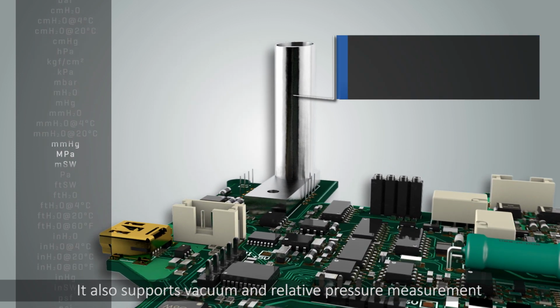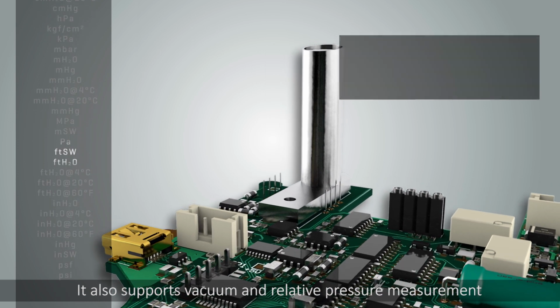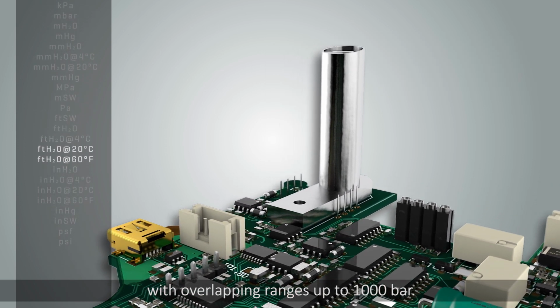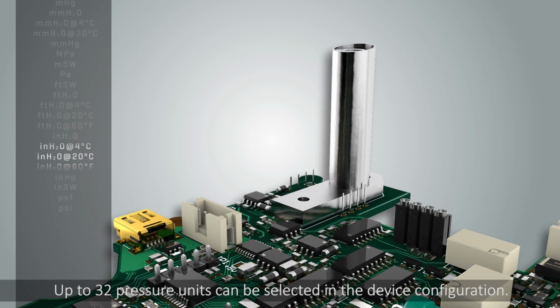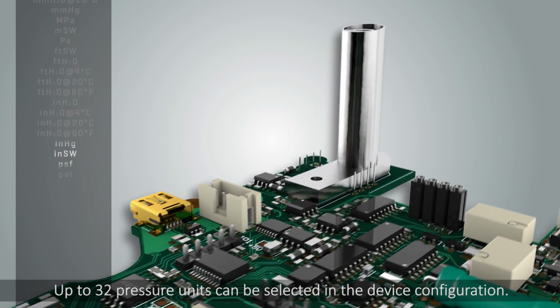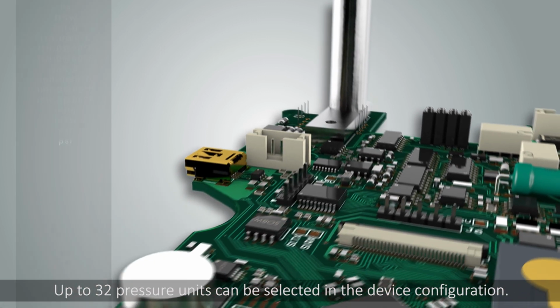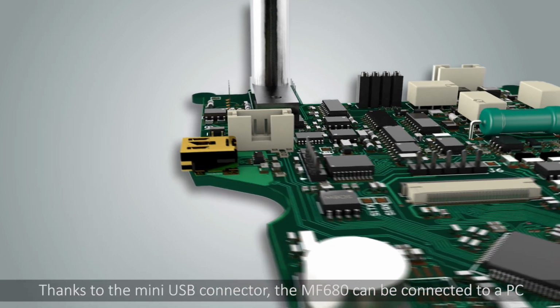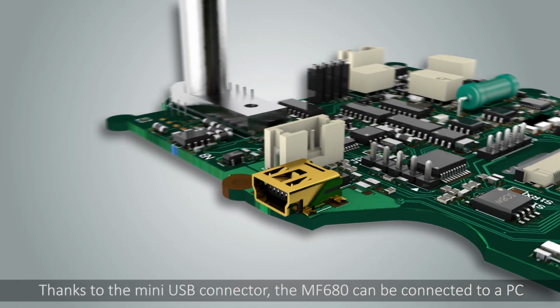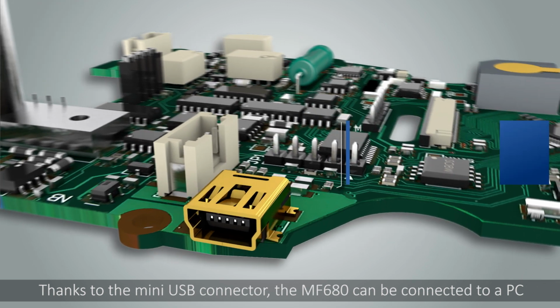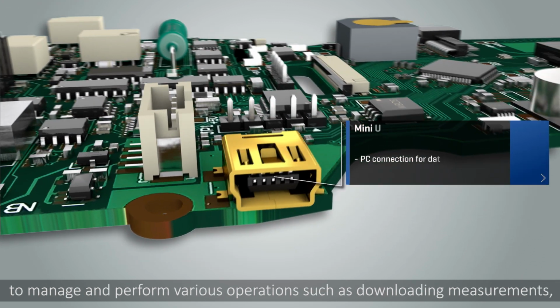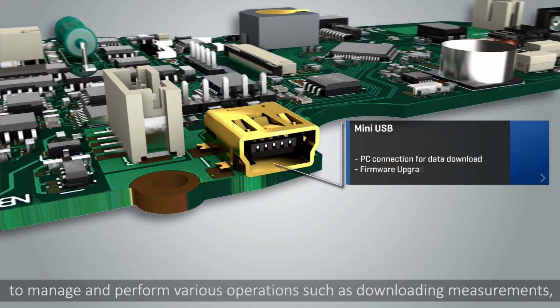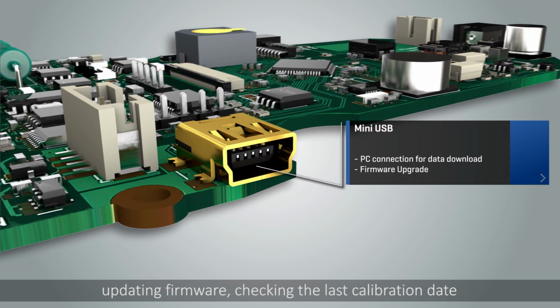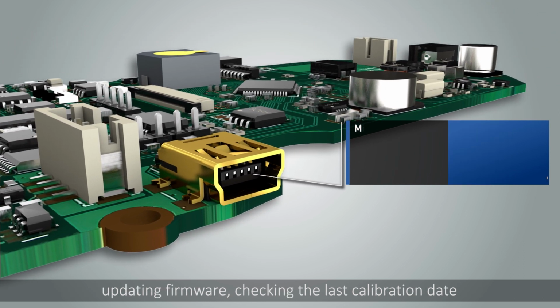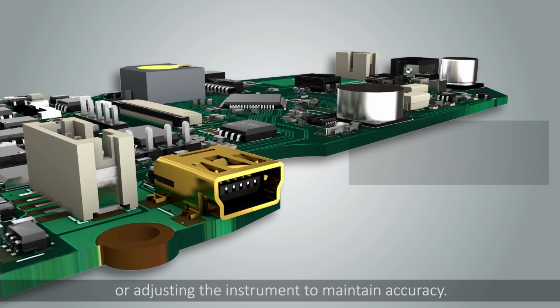It also supports vacuum and relative pressure measurement with overlapping ranges of up to 1000 bar. Up to 32 pressure units can be selected in the device configuration. Thanks to the mini USB connector, the MF680 can be connected to a PC to manage and perform various operations such as downloading measurements, updating firmware, checking the last calibration date, or adjusting the instrument to maintain accuracy.